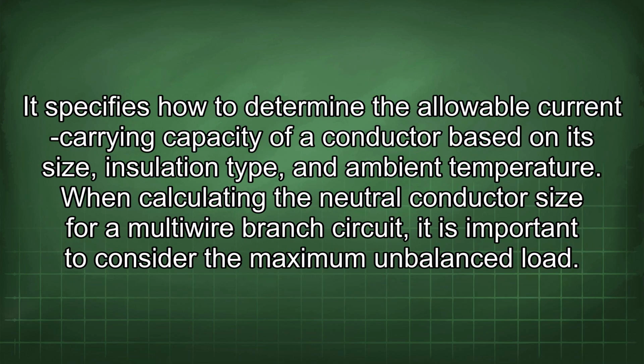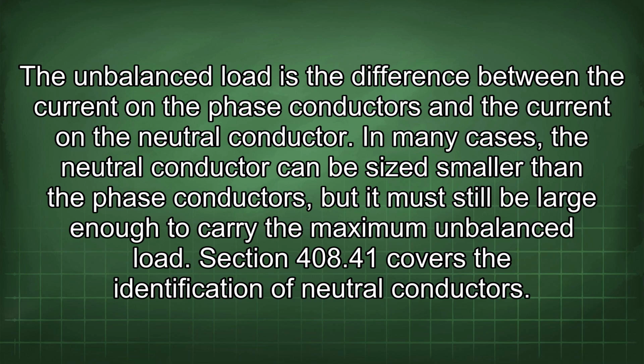It specifies how to determine the allowable current carrying capacity of a conductor based on its size, insulation type, and ambient temperature. When calculating the neutral conductor size for a multi-wire branch circuit, it is important to consider the maximum unbalanced load. The unbalanced load is the difference between the current on the phase conductors and the current on a neutral conductor. In many cases, the neutral conductor can be sized smaller than the phase conductors, but it must still be large enough to carry the maximum unbalanced load.